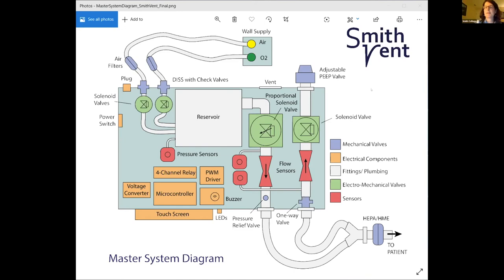I see, that's a commercial off-the-shelf solenoid valve. You didn't manufacture it yourself? Correct, we did not, this is a commercial one. It's not particularly expensive, maybe $75. This is the one purchased component we got that is not medical grade, because it's on the expiratory line. One could look for something that was medical grade, but because we didn't need that, it does have brass in it, and so we were able to get it for $75, and it's pretty easy to find.